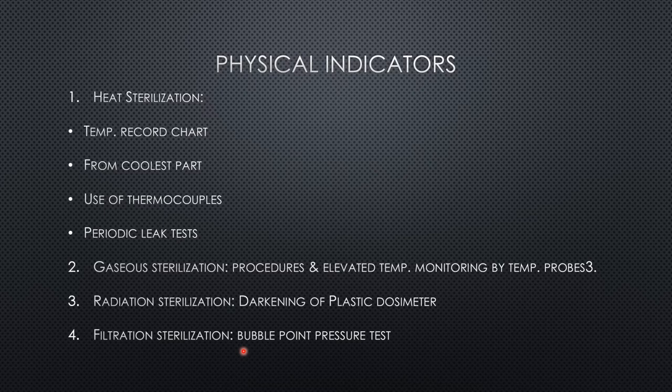When the gas pressure is further increased slowly, there is eruption of bubbles over the entire surface. The pressure difference here is related to the mean pore size. A pressure differential below the expected value would signify that the filter is damaged. Another test measures diffusion of gas through a wetted filter at a pressure below the bubble point pressure. If the diffusion rate is faster than expected, it indicates a loss of filter integrity. A filter is considered ineffective when an unusually rapid rate of filtration occurs.